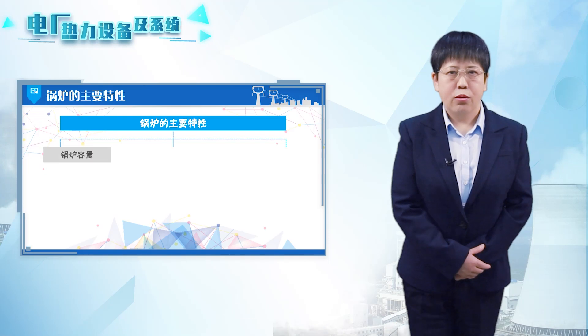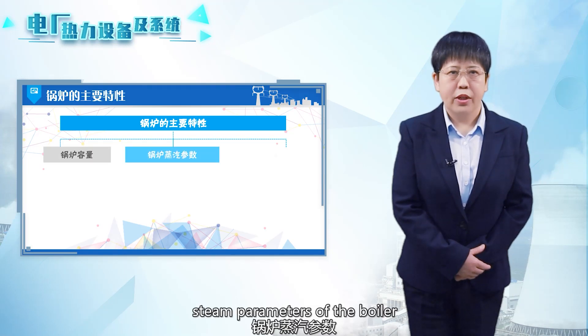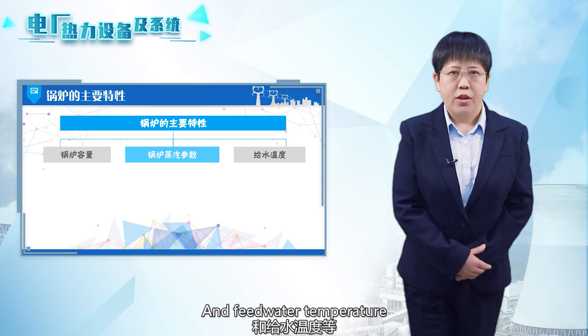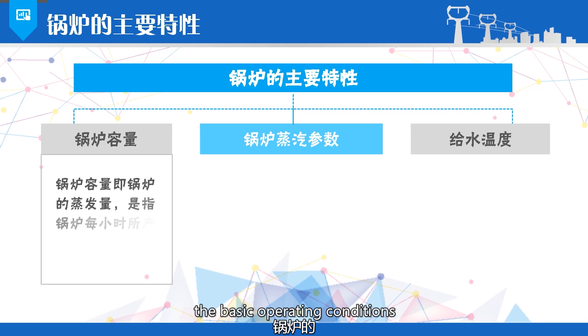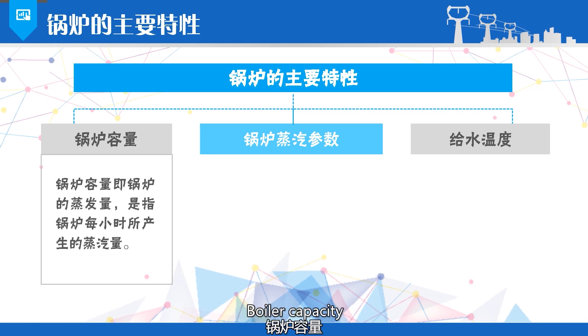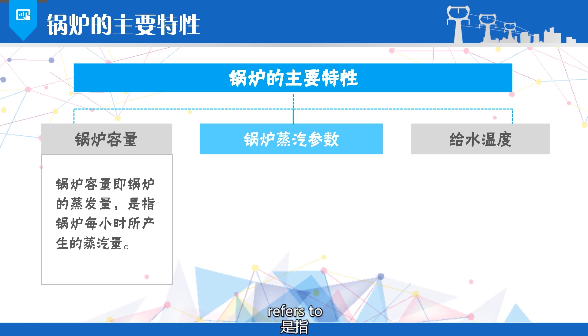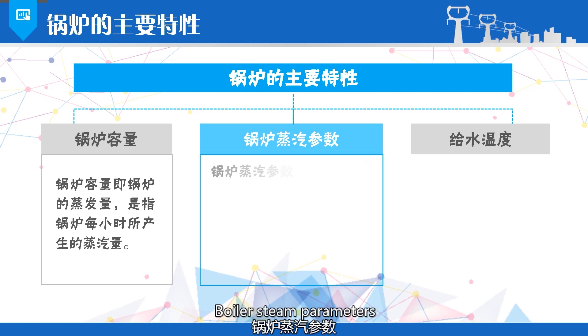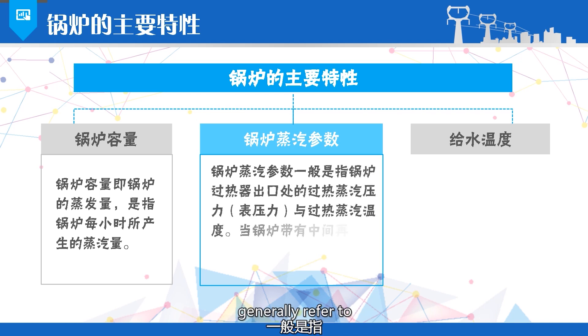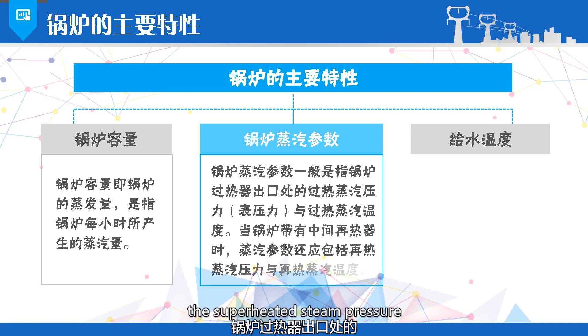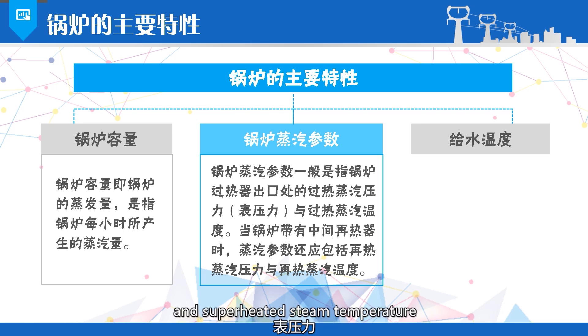The main characteristics of a boiler refer to the boiler capacity, steam parameters, and feed water temperature, which are used to describe the basic operating conditions of the boiler. Boiler capacity, also known as the boiler's evaporation rate, refers to the amount of steam produced by the boiler per hour. Boiler steam parameters generally refer to the superheated steam pressure and superheated steam temperature at the outlet of the boiler superheater.